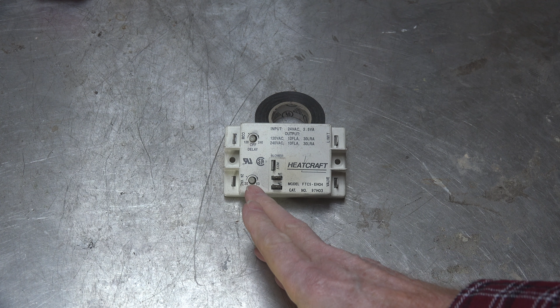It's just a timer. It has an on delay and an off delay. We could set from 30 seconds to 60 seconds in the on delay. That's going to determine whether the temperature coming out of the ducts when the air first comes out is warm or cool. If you set it too low, the duct temperature is going to be a little cool when it starts up. I would generally set this thing where the dot is. There's kind of a line here and then there's a dot over there. And that's where I'd set it to start, somewhere between 30 and 45 seconds. If that works, fine. If you're getting cold air, then you're going to want that delay a little bit longer. And that's all it is in the on delay.